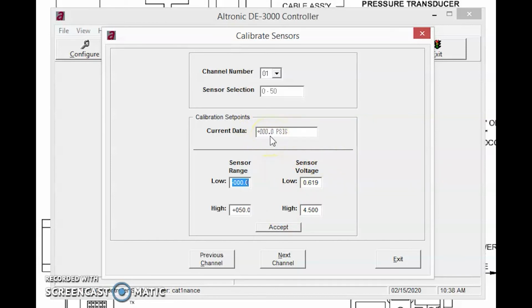Now we can do the same thing for the high side. So if we have a way to simulate a steady pressure, there are several different products on the market. Some people will use hydraulic pumps with certified test gauges so they can connect to the pressure transducer and pump the pressure up to full range, in this case 50 psi, and then they can measure their voltage, and then they can adjust and calibrate their high side as well. Works the same way as the demonstration for the low side.